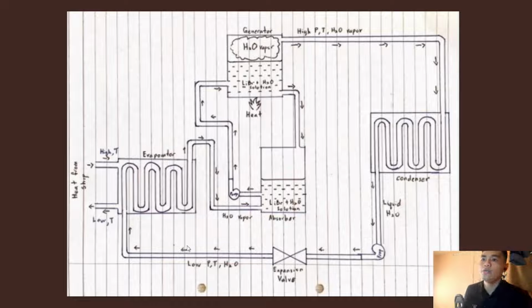Firstly, low pressure, low temperature H2O will move into the evaporator, and the evaporator needs to evaporate the H2O. So the heat from the ship, which is from the combustion engine, with high temperature will move to the evaporator and leave with low temperature. And then the vaporized H2O will move to the absorber. In the absorber, we have the lithium bromide solution and H2O solution, and then it will be pumped up to the generator using a pump.